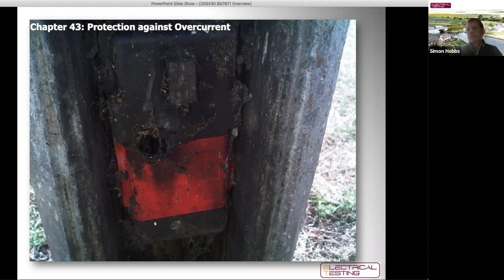Then we move to chapter 44, rapidly expanded over the last few editions and amendments, dealing with overvoltage. Overvoltage can occur generally through atmospheric conditions, i.e. lightning strikes, and it can also occur through switching on the high voltage side of the network, reflecting through the transformer onto the low voltage side.